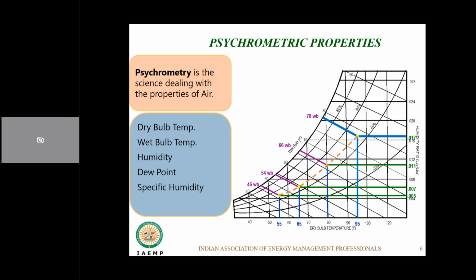I've understood. Thanks. So that is why, when you need to mention a relative humidity, it has always to be associated with its dry bulb temperature. Yes. Relative humidity in itself has no meaning unless you know its dry bulb temperature. I can say relative humidity is 100%, but I will never know 100% at which temperature, what are the other properties, unless I know the dry bulb temperature. Correct. Okay. Thanks. With your permission, I move ahead.